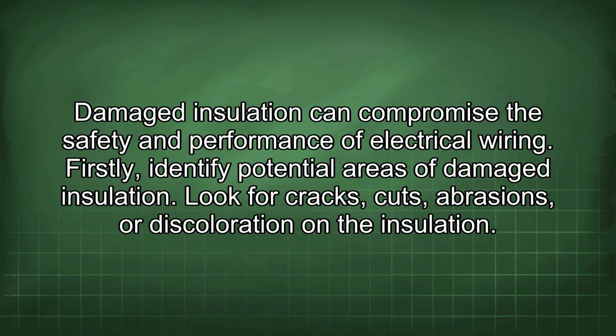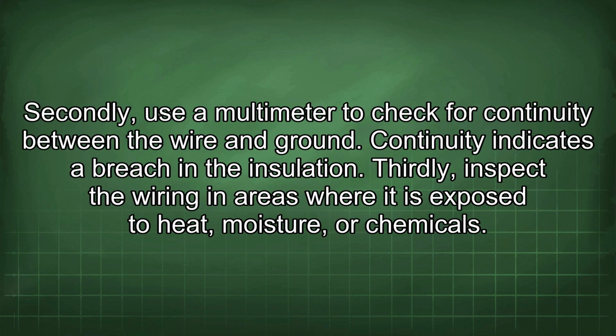Damaged insulation can compromise the safety and performance of electrical wiring. Firstly, identify potential areas of damaged insulation. Look for cracks, cuts, abrasions, or discoloration on the insulation. Secondly, use a multimeter to check for continuity between the wire and ground. Continuity indicates a breach in the insulation.